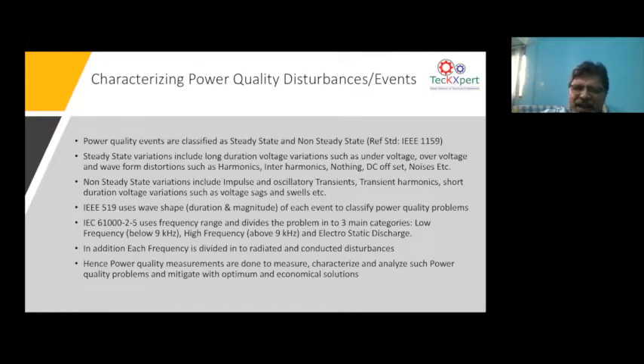Now, if you go to higher and higher switching frequencies, then you come across the high frequency category. The high frequency category is substantially electromagnetic interference. We cannot call it harmonics. Harmonics are at frequencies that remain in the low frequency spectrum, say up to the 50th order or the 100th order, below 9 kilohertz, and can be treated as harmonics. But above 9 kilohertz, we have to look at noises or electromagnetic signals of higher frequencies. Again, when a current or a voltage is going through a cable, as the frequency increases, it starts radiating. So there is again a radiated interference.